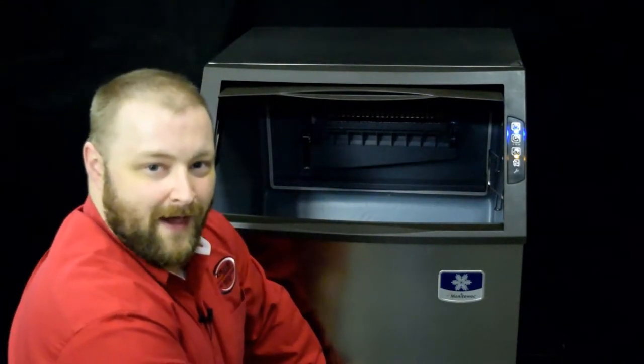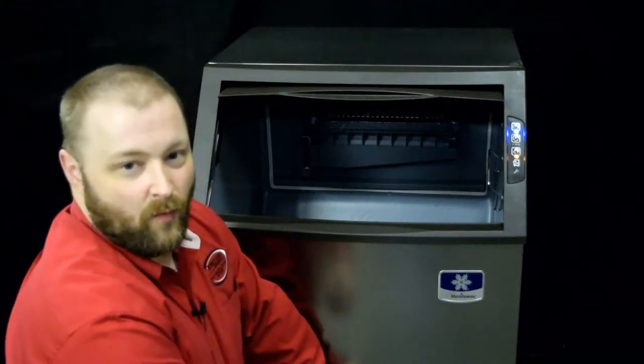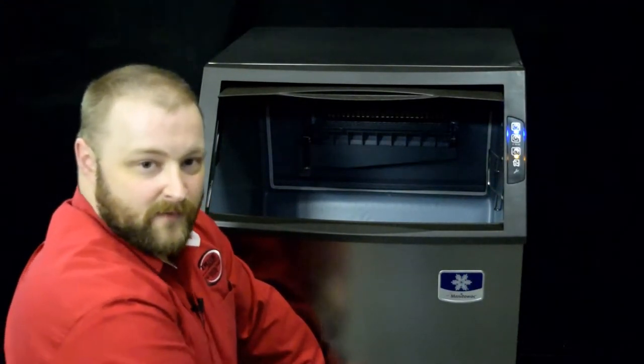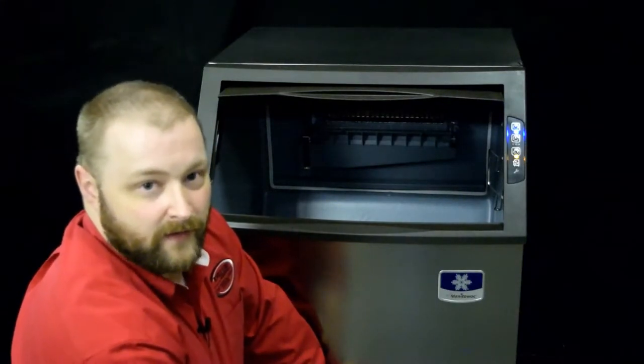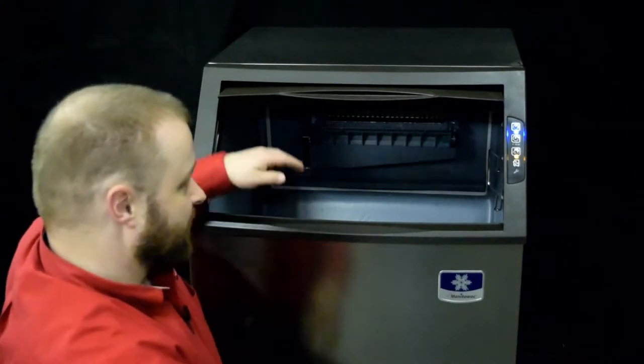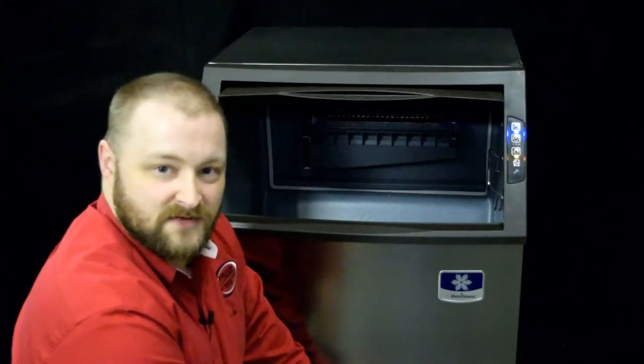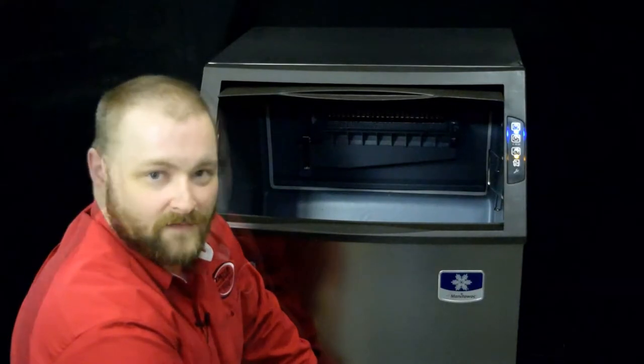Now what's happening with the ice machine is that the water is mixed with the cleaning solution and the water pump is picking up the water and it's going through the water distribution tube at the top and the water is cascading down over the evaporator and that's how the ice machine runs the self-cleaning process. The cleaning process will run for about 22 minutes before it's complete.